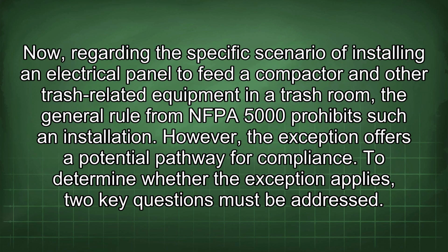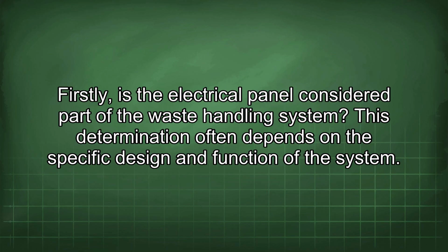Now, regarding the specific scenario of installing an electrical panel to feed a compactor and other trash-related equipment in a trash room, the general rule from NFPA 5000 prohibits such an installation. However, the exception offers a potential pathway for compliance. To determine whether the exception applies, 2 key questions must be addressed. Firstly, is the electrical panel considered part of the waste handling system?